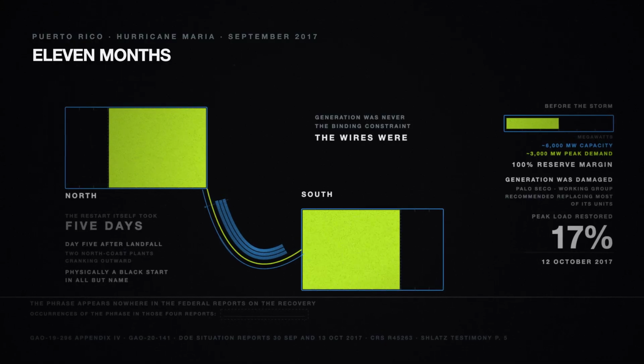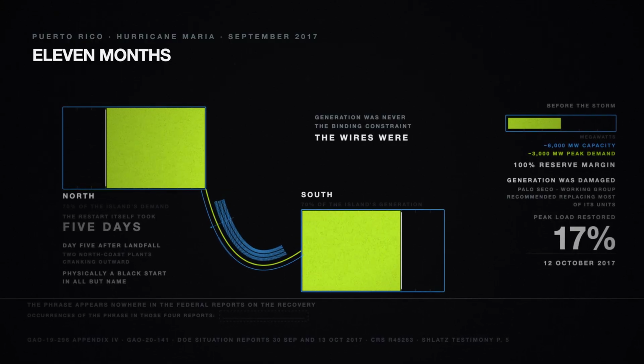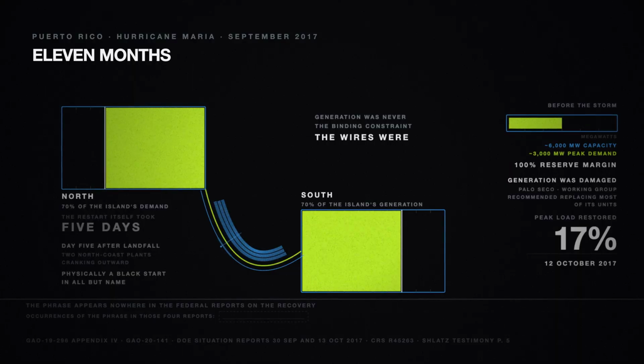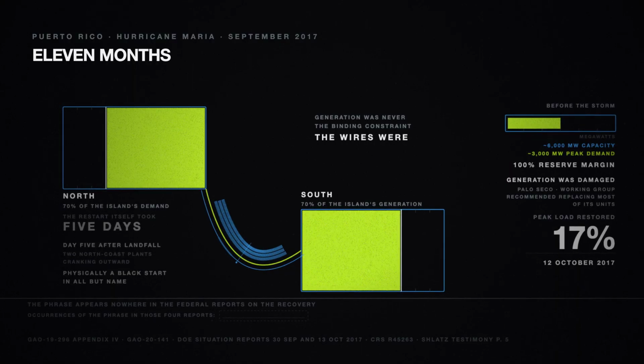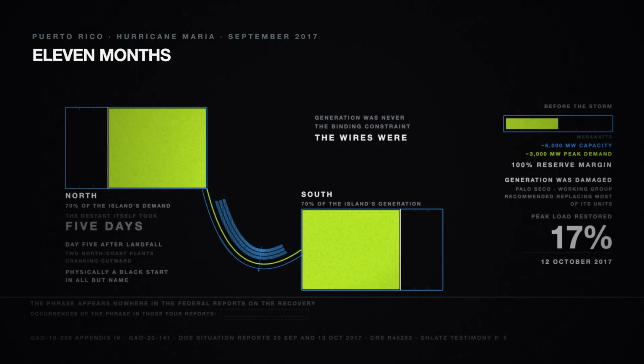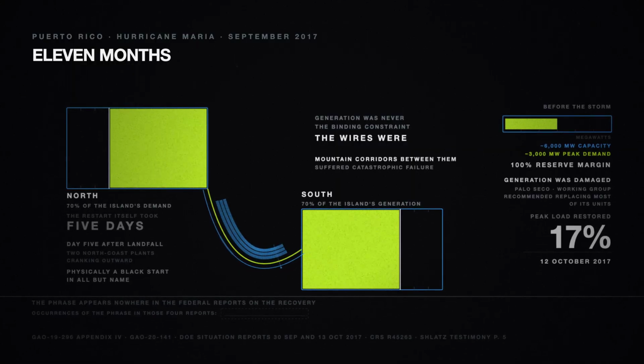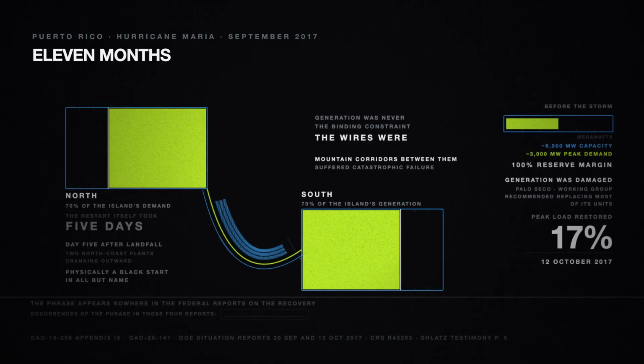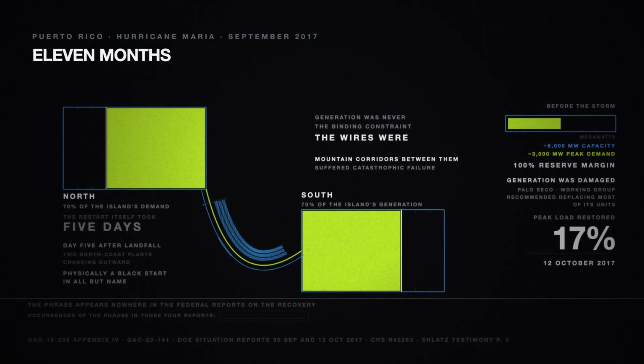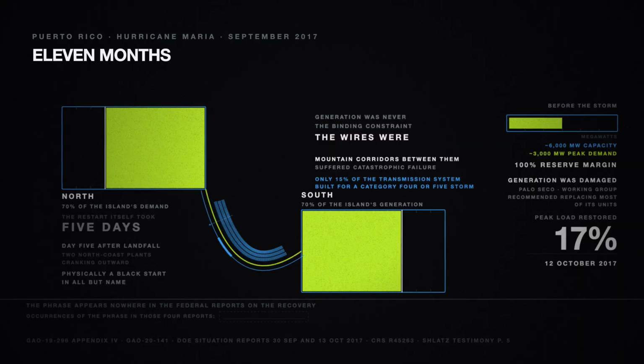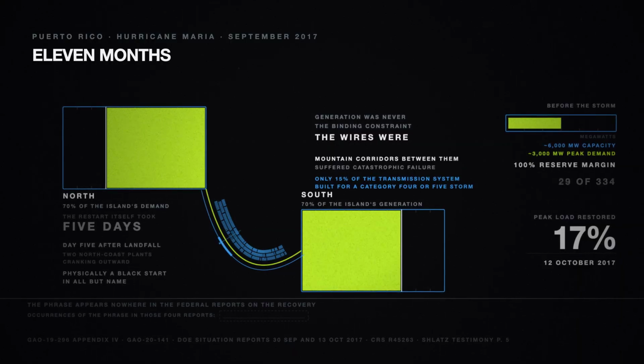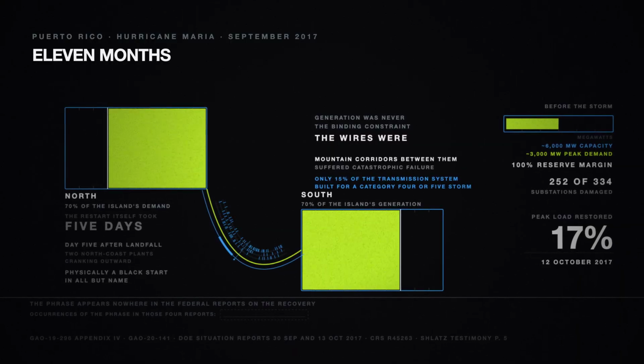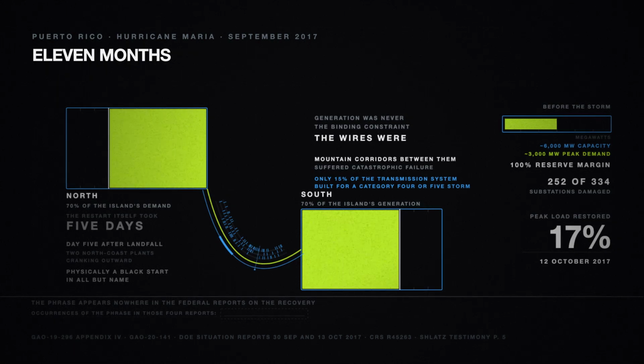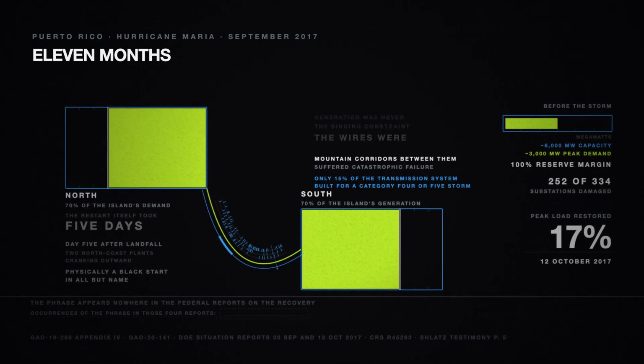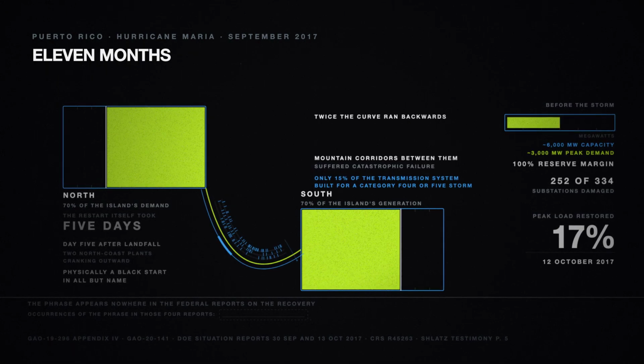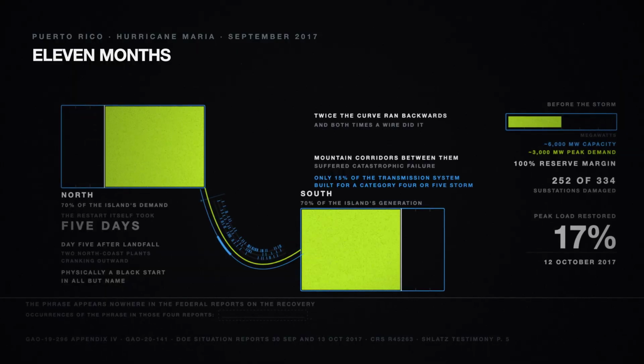The wires were. About 70% of the island's generation sits in the south, and 70% of its demand in the north. Between them run mountain corridors that suffered catastrophic failure. Only 15% of the transmission system was built for a Category 4 or 5 storm, and 252 of the utility's 334 substations were damaged. Twice the curve ran backwards, and both times a wire did it.